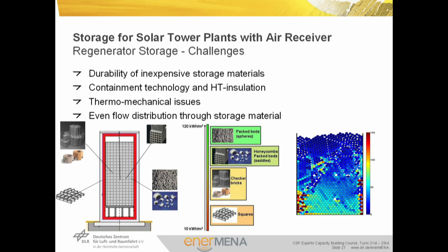Sensible storage materials are preferred for solar tower plants with air as working medium, but several challenges must be met. An important question is the durability of inexpensive storage materials. Another aspect is the containment technology and insulation. Due to temperature increases in the storage material, significant thermomechanical stress occurs. The distribution of flow through the storage material is also a key aspect to address.